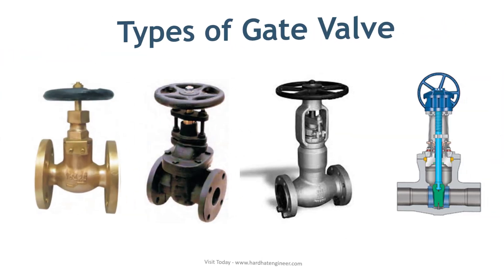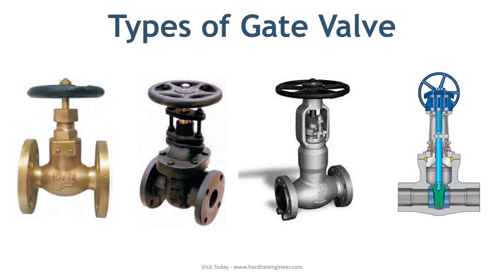Types of gate valve based on body-bonnet connection: 1. Screwed bonnet — this is the simplest design available and is used for inexpensive valves. 2. Bolted bonnet — this is the most popular design used in a large number of gate valves; it requires a gasket to seal the joint between the body and bonnet. 3. Welded bonnet — a popular design where disassembly is not required; lighter in weight than bolted bonnet counterparts. 4. Pressure seal bonnet — used extensively for high-pressure, high-temperature applications; the higher the body cavity pressure, the greater the force on the gasket.